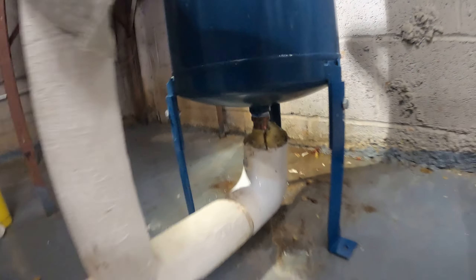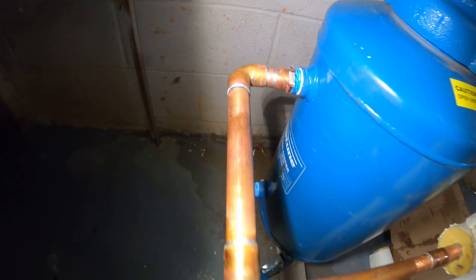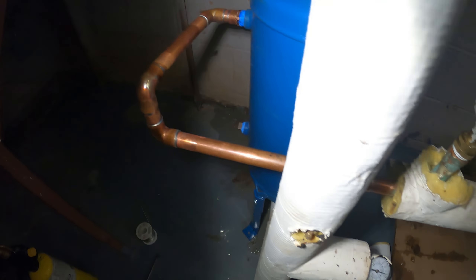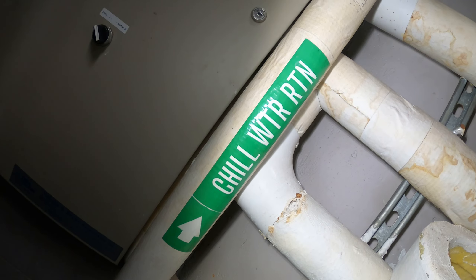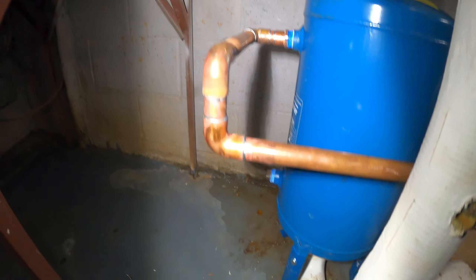We got this cap — we need to make sure we close onto here, so we're just going to tighten that down with the gasket inside. We also have a little pressure gauge right here. Got the gauge back on, going around and in, everything's tightened, we got the cap here, we got about 110 pounds of pressure, and the water valves are open.